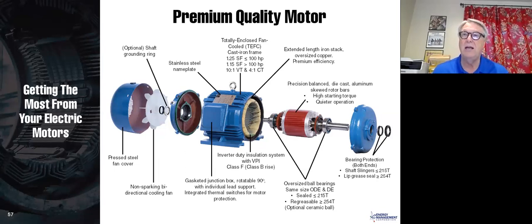Extended length iron stack, as we go around this thing clockwise, an oversized copper. The way you know you're getting that is to buy a premium efficiency motor. A premium efficiency motor tends to run at lower temperatures and last longer, in addition to providing energy savings. Now down here we have precision balanced die-cast aluminum skewed rotor bars. You see how those rotor bars are kind of skewed? They're crooked, they're at an angle. Well, that angle basically makes this motor run smoother and gives you more torque on starting. So a smoother motor means your bearings are going to last longer.